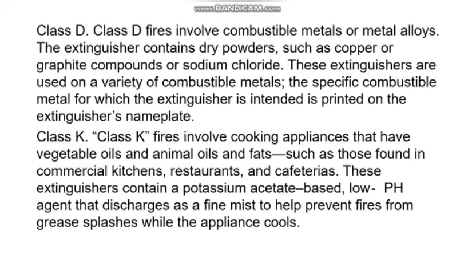Next is Class K. Class K fires involve cooking appliances that have vegetable oils and animal oils and fats, such as those found in commercial kitchens, restaurants, and cafeterias. These extinguishers contain a potassium acetate-based low pH agent that discharges as a fine mist to help prevent fires from grease splashes while the appliance cools.